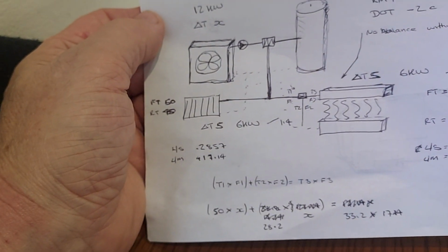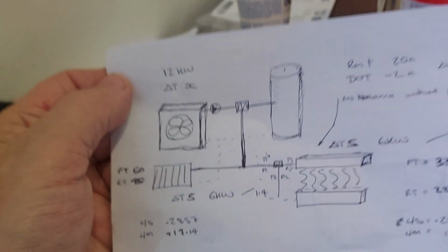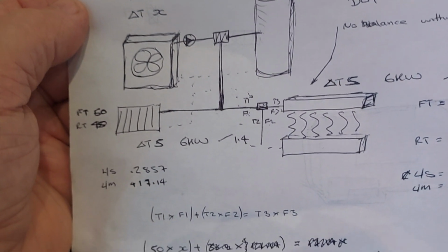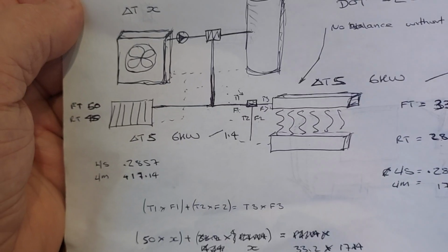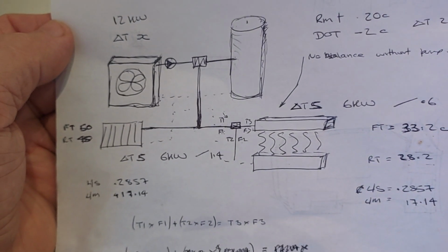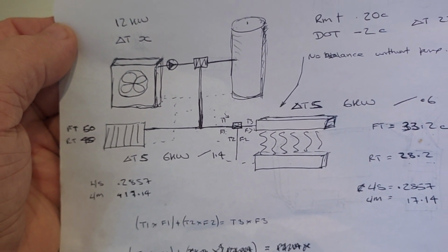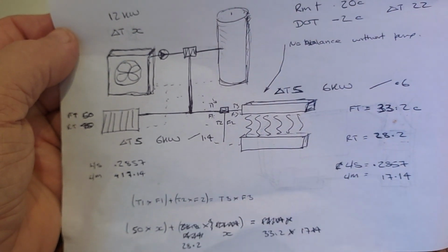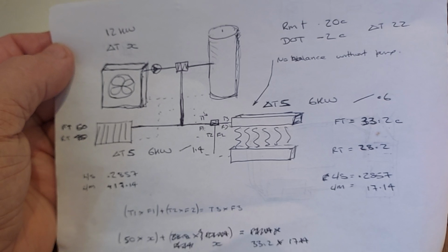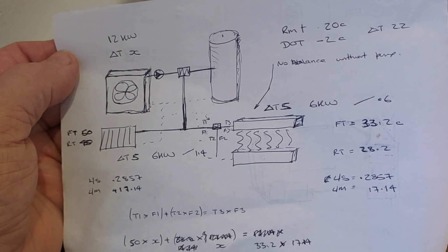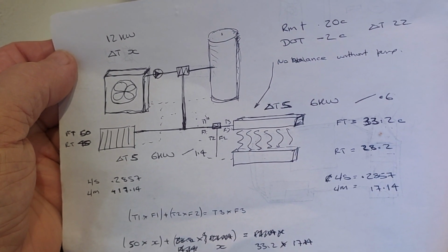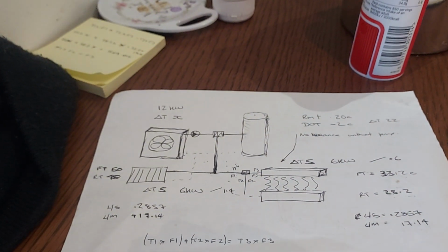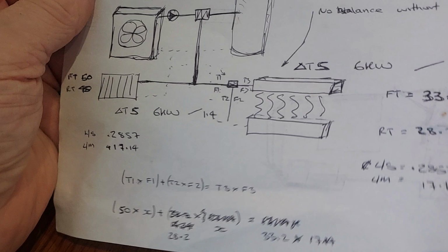We got a discrepancy of 3.57 litres, so we'd be squeezing another 3.57 litres per minute through our radiator system on top of everything else already at delta T5, and we know that it's not easy to get the flow rate of delta T5 through a radiator system. So it is my opinion that for this system to work, we would need to have some kind of hydraulic separation after the heat pump, as most manufacturers would recommend.